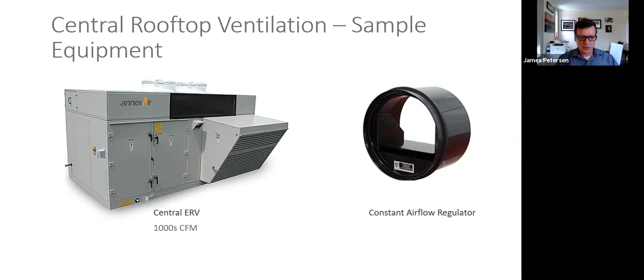We'll get into more considerations for these three types of ventilation approaches. They all incorporate heat recovery or energy recovery—this is energy recovery 101. Basically, you have the exhaust air stream in proximity to the fresh air stream, and they're meeting at a heat exchanger. By the miracle of modern science, they're exchanging heat and moisture at the heat exchanger, but they're not recirculating air.